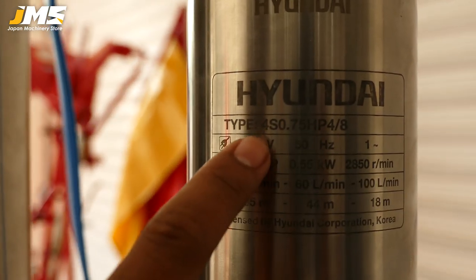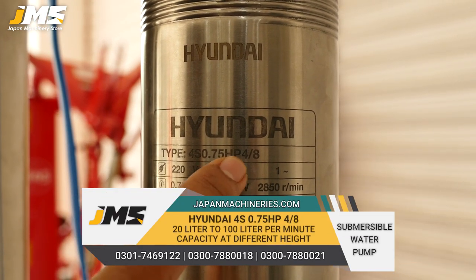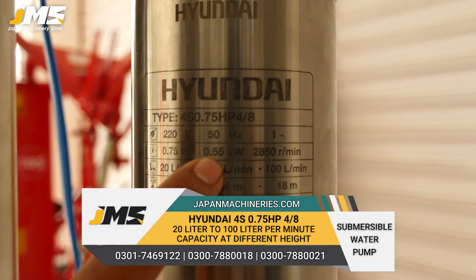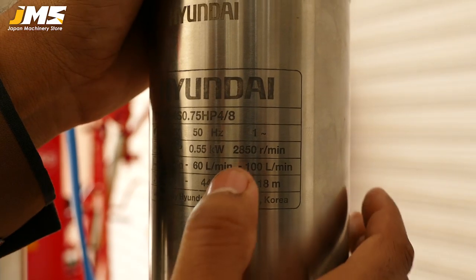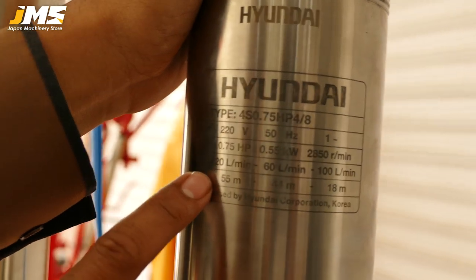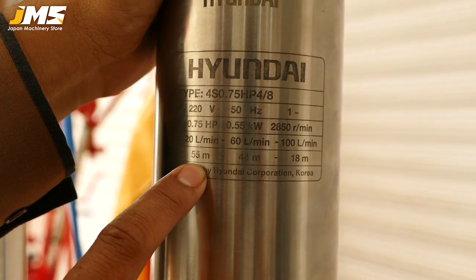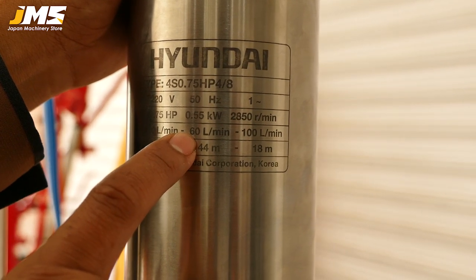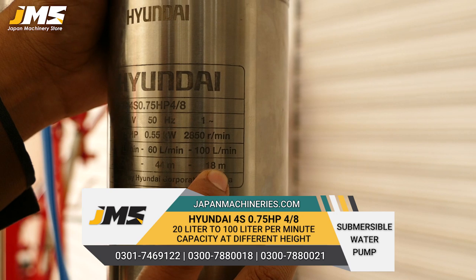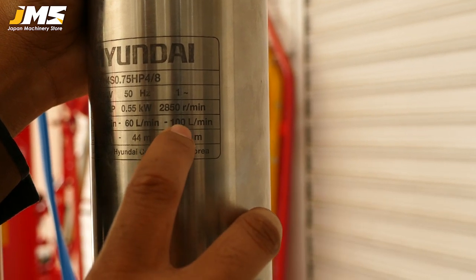The first model is 4S 0.75 HP. This is a single phase, which works on 220V. The head is 55 meters. At 55 meters it gives 20 liters per minute, at 44 meters it gives 60 liters per minute, and at 18 meters it gives 100 liters per minute. If the depth is reduced, you will get more flow and faster flow, so at the top it will be 100 liters per minute.